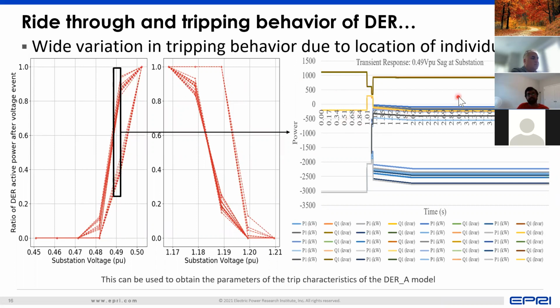And pretty much you see that the response is quite widely distributed, and it's even more so for a high voltage side. And we saw that voltages tend to rise as you have more DER coming in, which means that for a small rise in voltage, where this is a voltage swell that occurred, maybe because of a loss of load somewhere else in the system where voltage suddenly rises, you can have this tripping behavior that occurs where in one place you could have all the DER riding through, whereas in another feeder, you could have only 20% of the DER that were able to ride through.